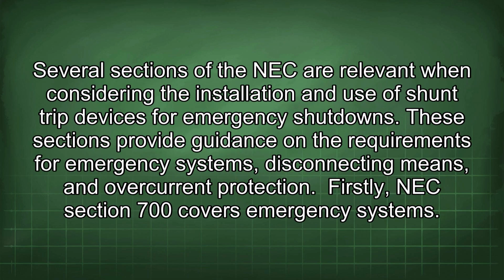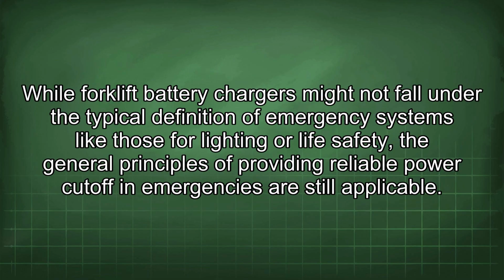Several sections of the NEC are relevant when considering the installation and use of shunt trip devices for emergency shutdowns. These sections provide guidance on the requirements for emergency systems, disconnecting means, and overcurrent protection. Firstly, NEC Section 700 covers emergency systems. While forklift battery chargers might not fall under the typical definition of emergency systems like those for lighting or life safety, the general principles of providing reliable power cutoff in emergencies are still applicable.